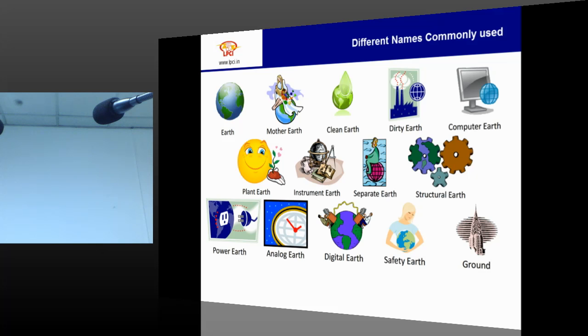This is a very complicated question, or the answer is complicated, because this is a point of argument always. But there are solutions. For example, in some countries, for sensitive electronic equipment, let's say for example like UPS, which will create third harmonics, or the computers are creating third harmonics, neutral current is more, so before UPS or maybe after UPS we put an isolation transformer. After the isolation transformer, neutral is not extended, so basically there is some solution for the neutral excess current.